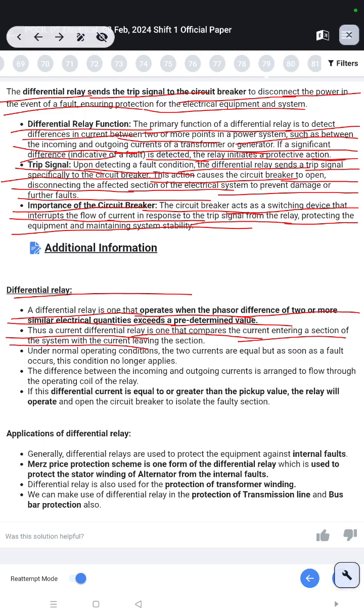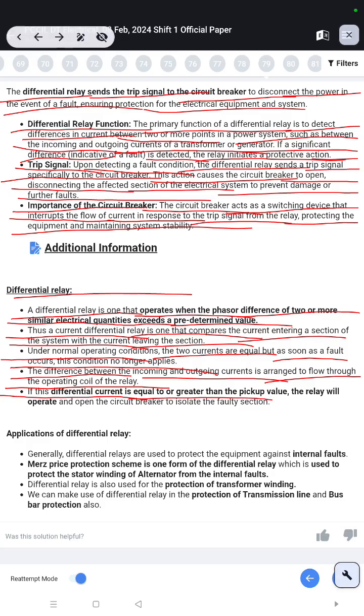Under normal operating conditions, the two currents are equal, but as soon as a fault occurs, this condition no longer applies. The difference between the incoming and outgoing currents is arranged to flow through the operating coil of the relay. If this differential current is equal to or greater than the pickup value, the relay will operate and open the circuit breaker to isolate the faulty section.